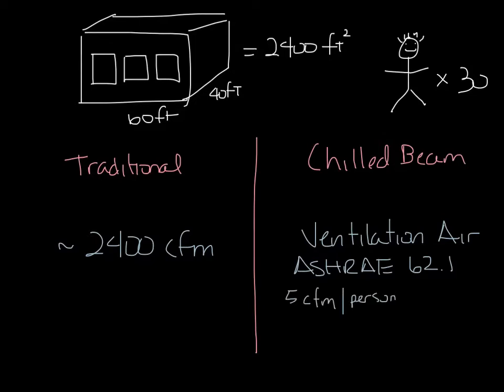and for this application, 0.12 CFM per square foot. You add all that up, and you come up with 438 CFM in this space.